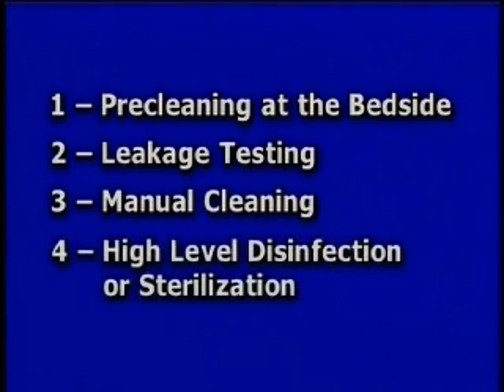High-level disinfection or sterilization is the next reprocessing step. High-level disinfection kills or inactivates any remaining vegetative bacteria, viruses, and fungi. It is important that you test the disinfectant solution regularly for potency and use it at the temperature and for the contact time recommended by the manufacturer. Also remember, disinfectant solutions are toxic. Wear appropriate personal protective equipment throughout the entire procedure and thoroughly rinse all disinfectant from the endoscope prior to the final alcohol flush drying procedure.